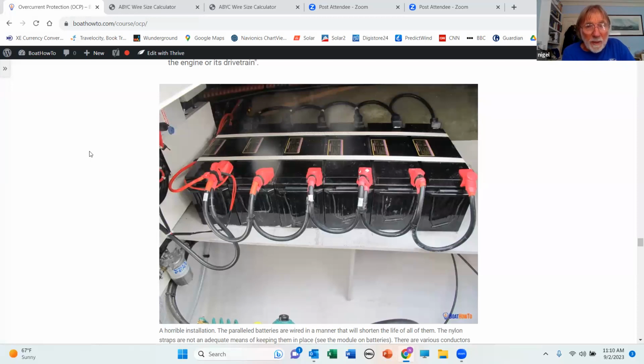Right. We've got more than 4 conductors coming off the battery post, so that's another standards violation. We've got multiple conductors coming here with not a sign of a fuse anywhere. So most of those are not adequately overcurrent protected. We've got some other issues here unrelated to the overcurrent protection, which I'm going to address now so I don't forget it.